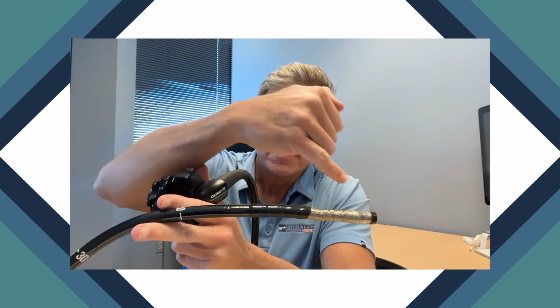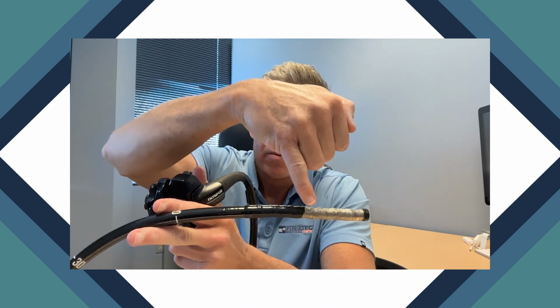So that angulation in all four directions is a very important step, not to be missed when they're performing the leak test. And when they're looking at the bending rubber bending section, the epoxy seals, if they're going to do a preventative maintenance inspection, when the seals start to turn gray, opaque, there's chips in the epoxies, or there's anything they can visually see on the outside, should it go in for repair? Yeah, so that's a really good question that a lot of people don't understand. So again, right here, the seal on the top of this is missing because the bending rubber's been cut off.